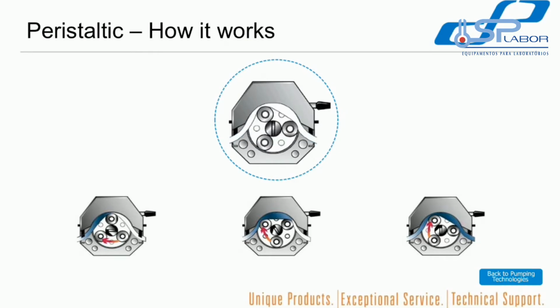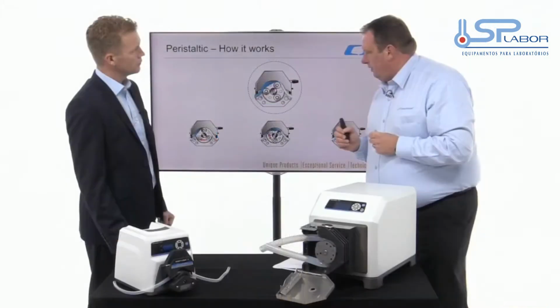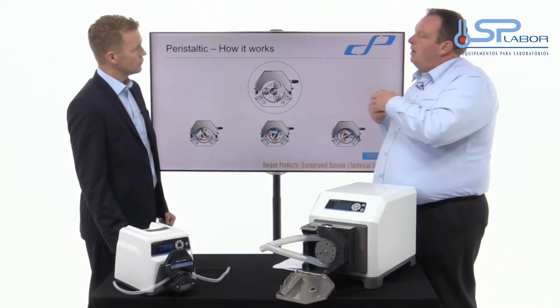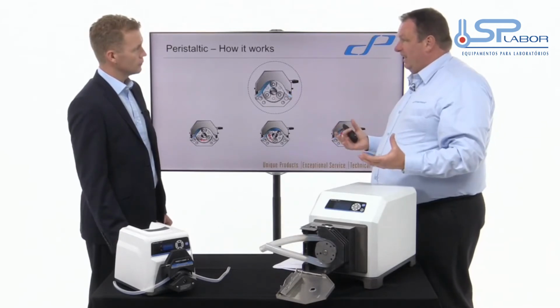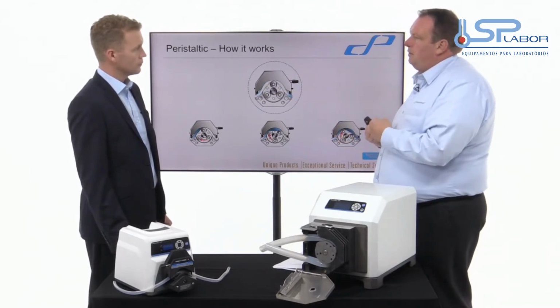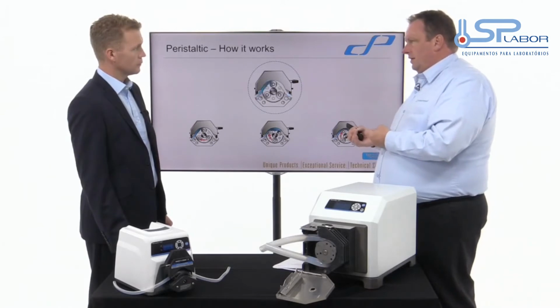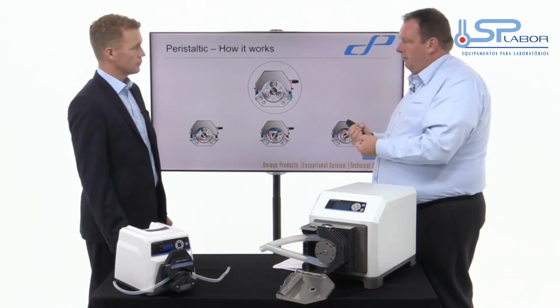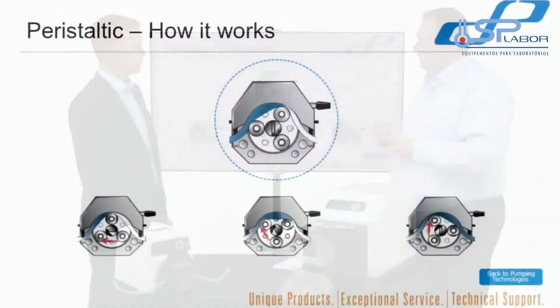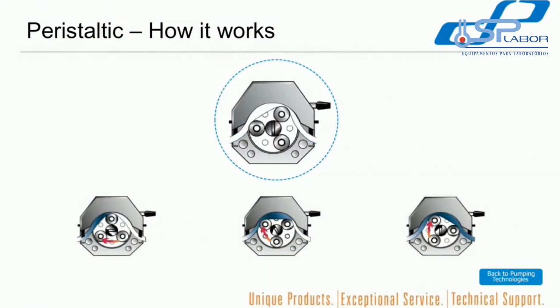Can these pumps dry run? Dry running is a very, very interesting concept, and yes, they can. Dry run means to run without any liquid in it. If you have pumps where you have metal-to-metal faces and things like that, no, they can become very damaged. One distinct advantage of these pumps is they can dry run. Because you have a roller reacting on a tube, squeezing a tube, it can do that all day long. There are no issues with metal-to-metal surfaces, there are no issues of unusual heat build-up, so they can dry run.